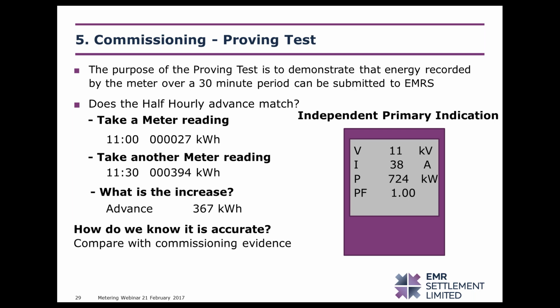So in this example, if the commissioning results made reference to an independent primary indication, which can be seen on the right, and it was showing a prevailing load instantaneously of 724 kilowatts, should that have been a constant over the 30-minute period, we would expect to see around 362 kilowatt hours. This is comparable to the advance demonstrated in the cumulative register technique and helps to validate that figure. Finally, we will check that the half-hourly data presented to either data collector or EMRS matches this value. We would expect to see a half-hourly value of approximately 360 to 370 kilowatt hours. Should these values match, this part of the metering test would be passed.